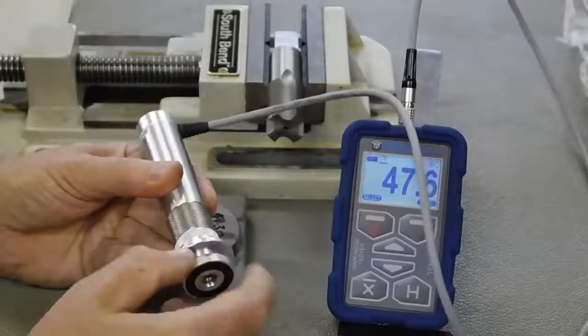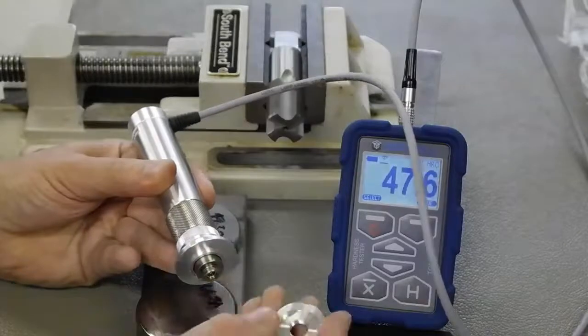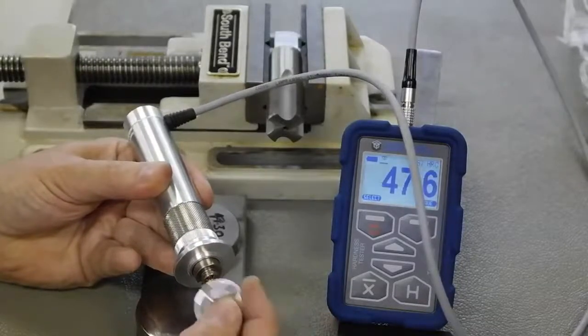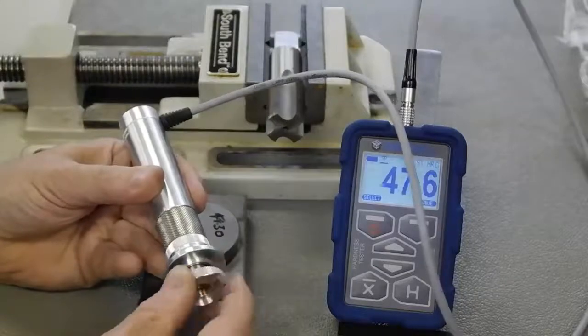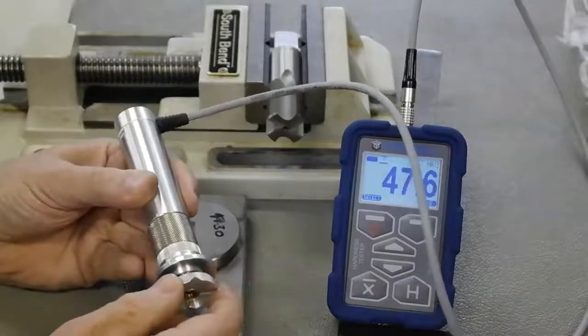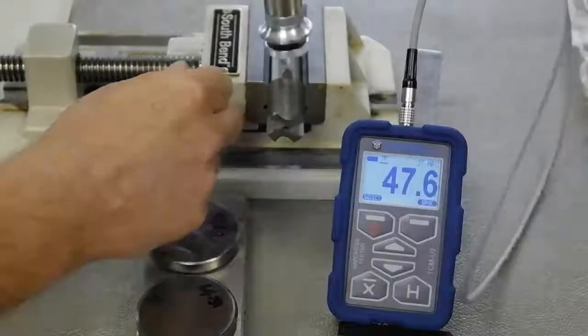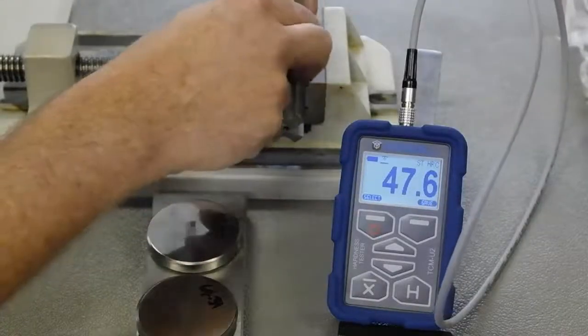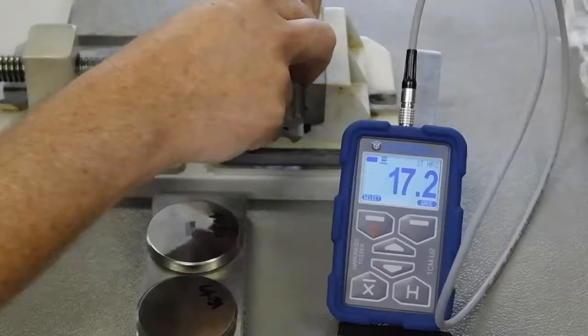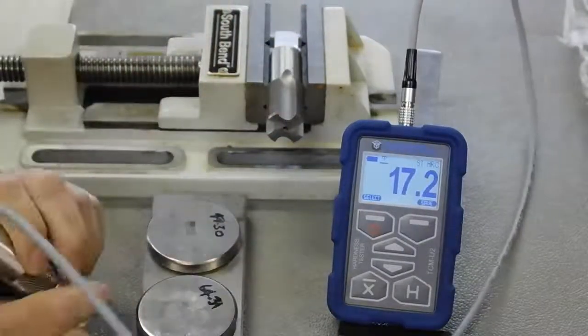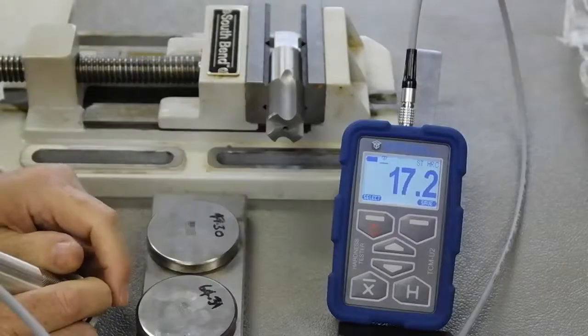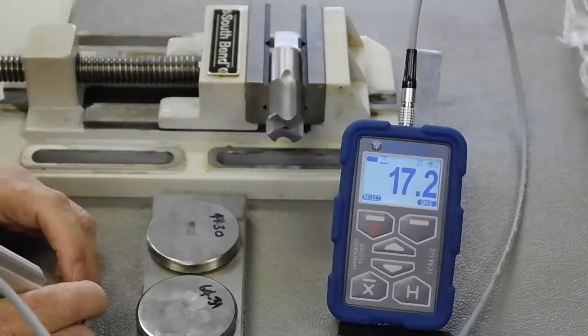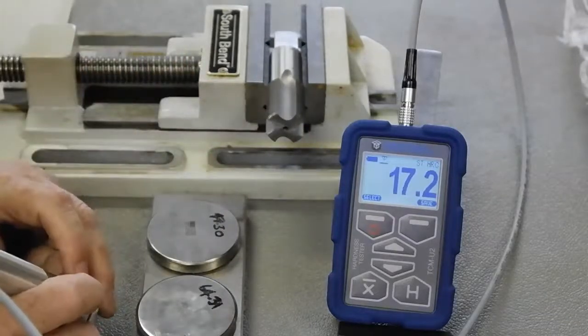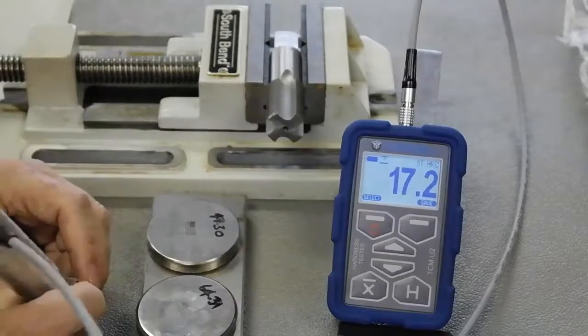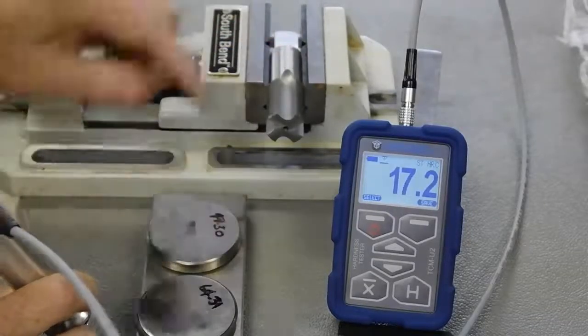So if I screw off the end of the puck, here I have 2 V-grooves, a larger one and a smaller one, clearly for different cylinders. On my tap, it's cylindrical of course, so I'm going to use the smaller of the 2, and I do a test. I know the tang is very, very soft, and here it is actually doing a test, and it's showing 17.2. The device we certify for accuracy down to 20 HRC, up to about 65, so very hard down to soft. But you can see the device can also check lower, but you're going to get more variations at the very low end. I just wanted to show that this is going to show very soft.